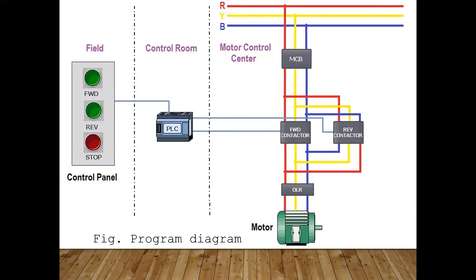Protection must be given so the motor cannot run in both directions simultaneously, even if the operator tries to press both buttons at the same time. We call this interlocking. In the PLC field side, we have three inputs — forward button, reverse button, and stop button — and two outputs: forward contactor and reverse contactor. Remember these numbers: three inputs and two outputs, as we will use this for the programming.